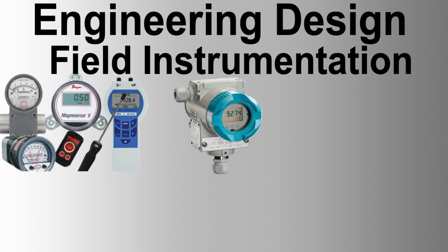Electrical testing. Electrical testing must be performed on all electronic instruments to verify their performance and compliance with the specified requirements. This includes insulation resistance testing, continuity testing, and functional testing of electronic circuits. Test reports must be provided to the purchaser for review and approval.